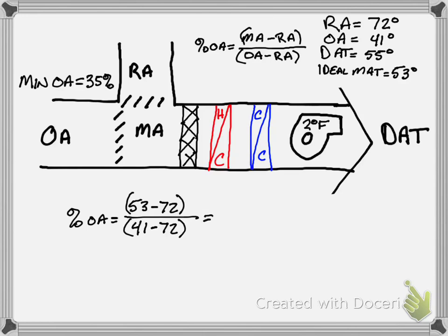So that's going to equal negative 19 over negative 31 which equals 61%. Now whenever we get a percentage and we need to determine whether our economizer can meet this, we have to understand two different things. One, what's the maximum outside air percentage that we can have? Typically in a functioning system, this is 100%. If you have a deficient system, this could be less than 100% if you have broken dampers or linkages.